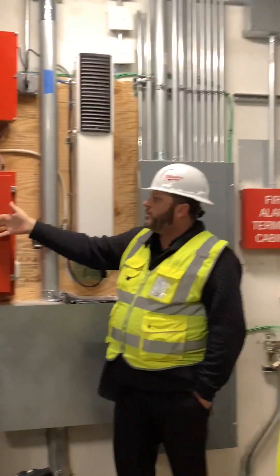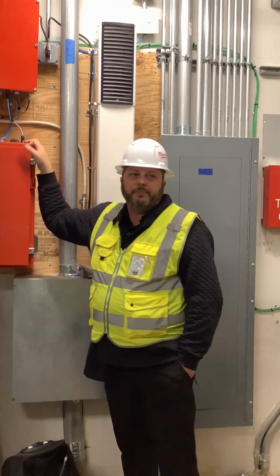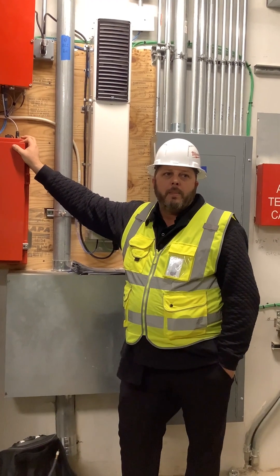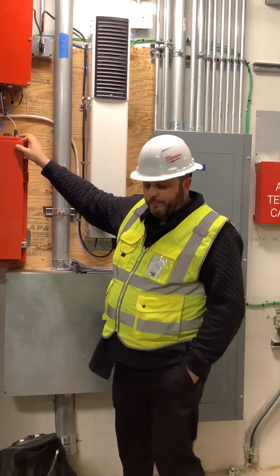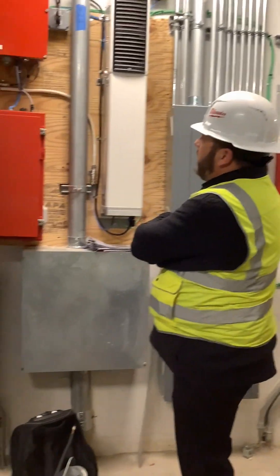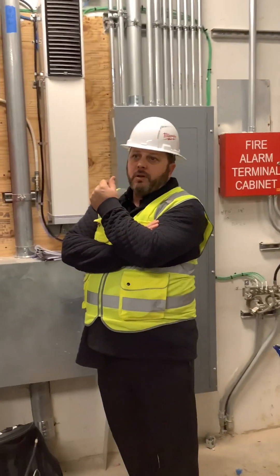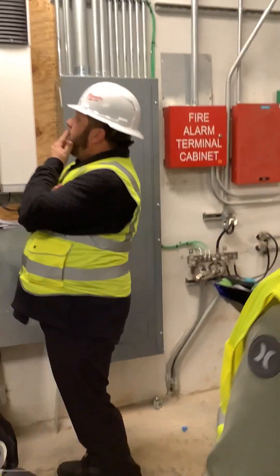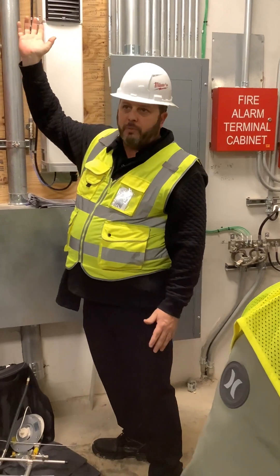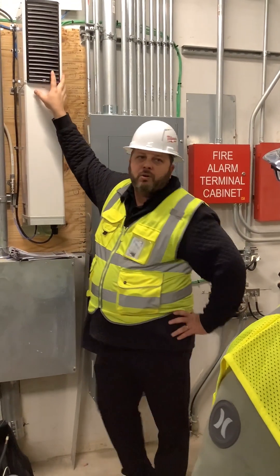Except for that one where we're getting a battery fail — not just because it's unplugged. If it does come unplugged temporarily, what you'll get is an AC power fail, and then when the battery's removed, you'll get the battery fail. If you needed to do something, you can have it unplugged for a couple of minutes, but plug it right back in. But normally, once everything's set, there's no need to touch it.